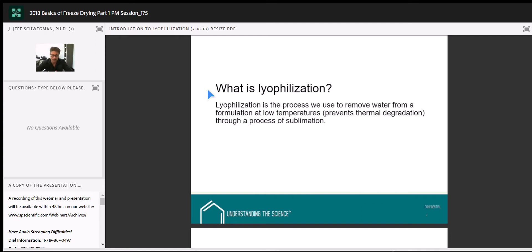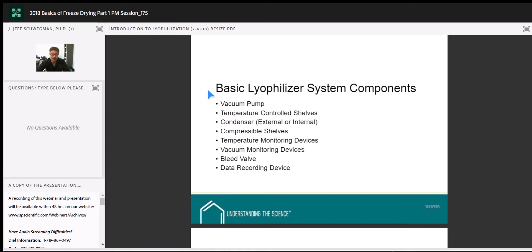Some system components found on almost every freeze-dryer: there must be a vacuum pump. Vacuum — specifically the change in pressure — is actually the driving force of freeze-drying, and we'll talk more about that. We've got to create a high-vacuum, low-pressure system within the chamber to get freeze-drying to occur in what we call bulk flow.